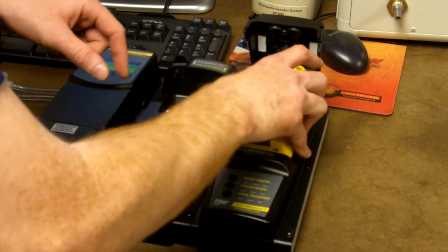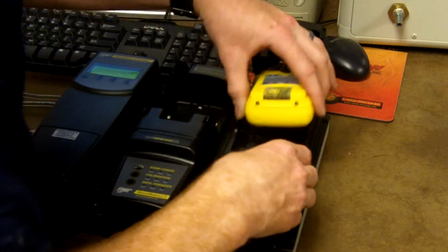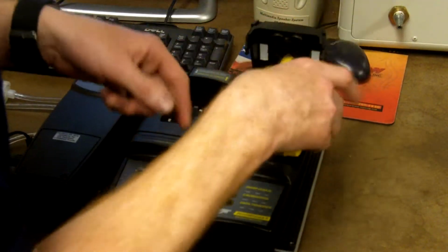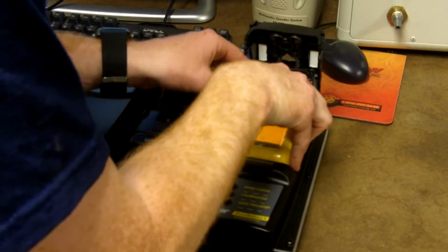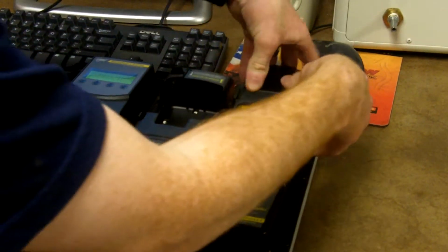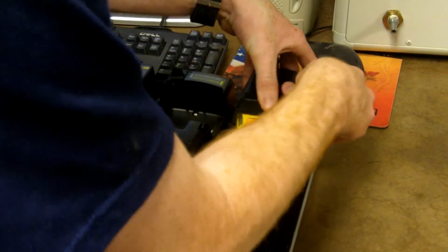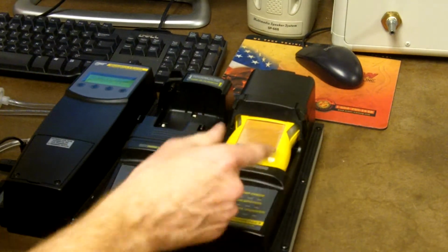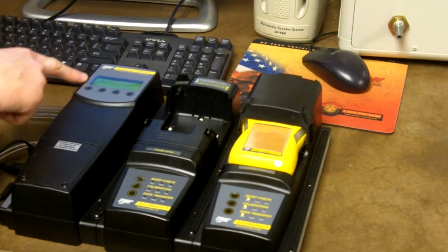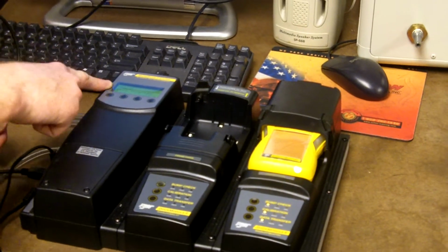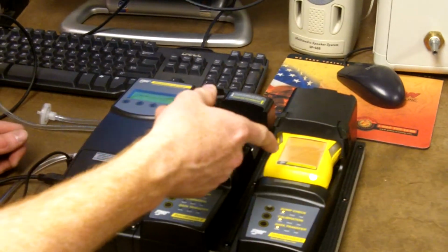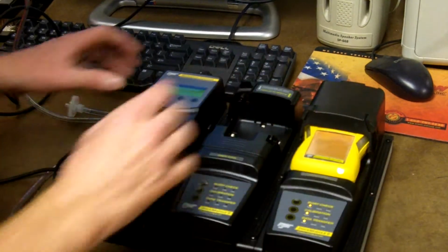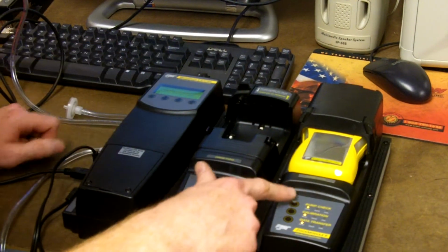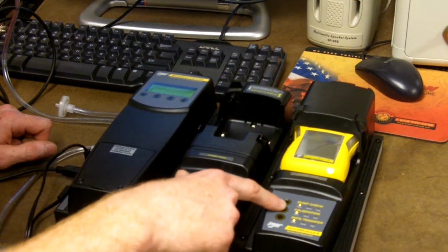So I open up this right station. It says the gas alert Quattro. So I put this face down. I disregard that. You want to put it face up. And then we click on the top portion to it, and it should snap in. And so from here, it will display that it senses that it has a gas detector inside. So now on my options, I have bump check, calibration, data transfer. So I'm going to hit calibration.